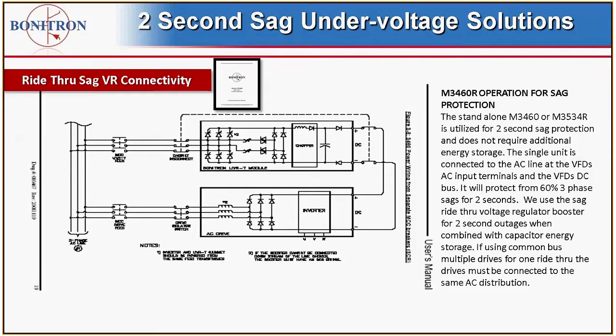If you're tying the sag ride-throughs to multiple drives, we would size the sag ride-throughs to the total drives on the common bus. One critical thing about sag ride-throughs is that any of the drives that are tied to the ride-through unit must be on the same AC feed as the ride-through unit, and all of the drives are tied to.